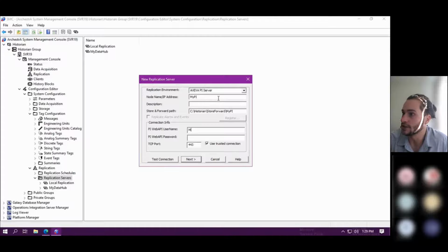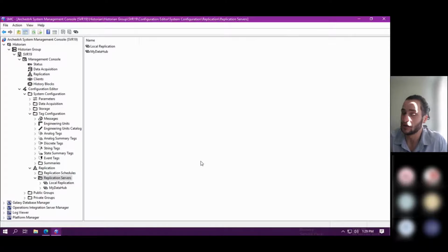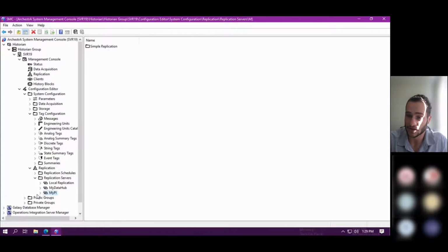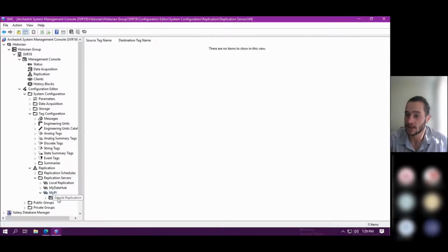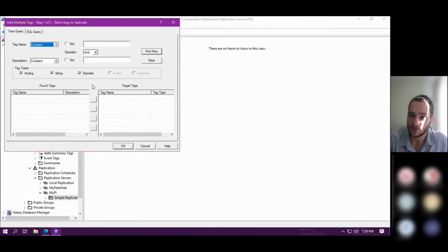Once the appropriate data has been chosen and replicated, you will then be able to find that data inside of the client tools like PI Vision. And one of the neat things about this feature is that you could actually even rename the tags when you set up replication if desired. So it gives you control over how the tags would be named inside of the Pi system and possibly label them differently from how they are in the AVEVA Historian.